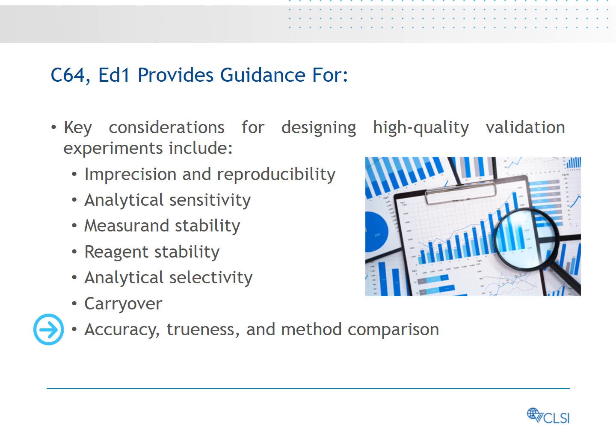Accuracy, trueness, and method comparison: evaluation of trueness, i.e., the magnitude of agreement with a reference system, is the preferred method of accuracy assessment. To evaluate accuracy, the developer should perform method comparison experiments with multiple runs over a minimum of five days. Method comparison studies should use individual native matrix samples that represent the spectrum of physiological states, both normal and pathological, expected in the intended test population.